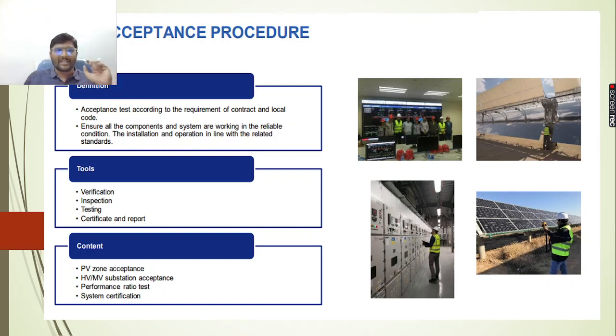Next, acceptance procedure. First and foremost, you need to make verifications. Then you need to do the inspection using the quality assurance and quality control team. Then you need to do the testing operations, as well as inspection of those testing operations with the quality assurance and quality control team. Then you need to make a certificate and report based on it. When you're doing the acceptance procedure, you need to classify the photovoltaic zones, and for each zone we need to make acceptance criteria. We also need to do the high voltage and medium voltage substation acceptance tests, the performance ratio test, and the system certifications. So we need to ensure all the comprehensive systems are working in reliable conditions, and that the installation and operations are in line with the related standards.